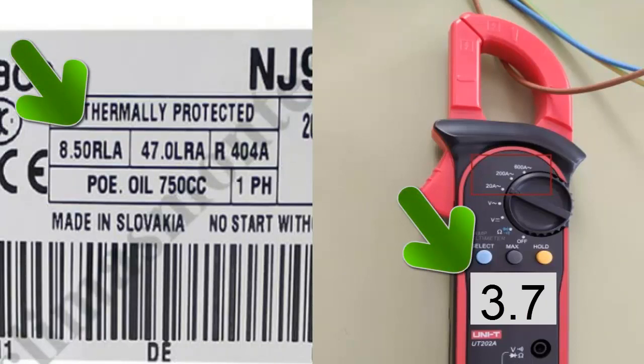Step 4. With the equipment turned on and after several minutes, compare the value measured by the amperometric clamp with the regular consumption of the unit. If the clamp's value is lower, it may indicate a lack of refrigerant.